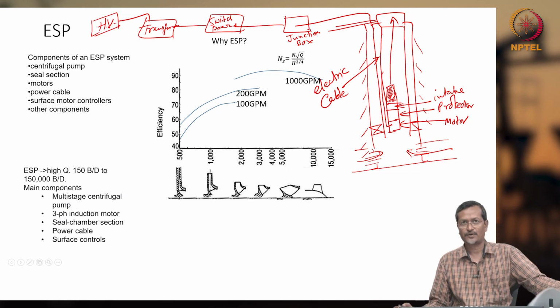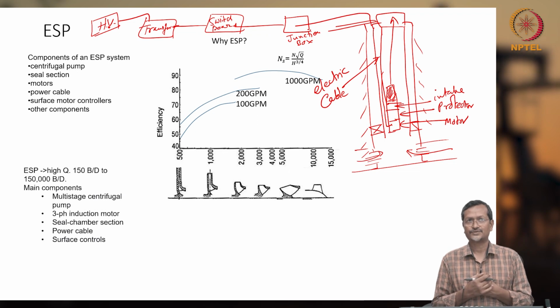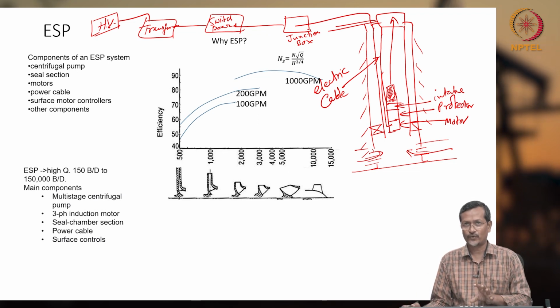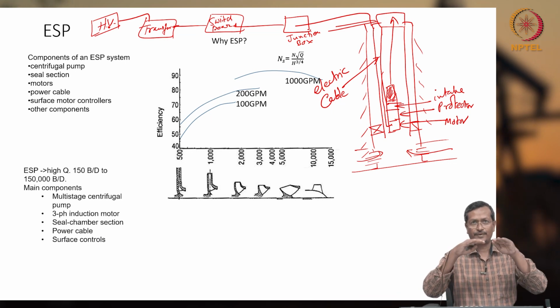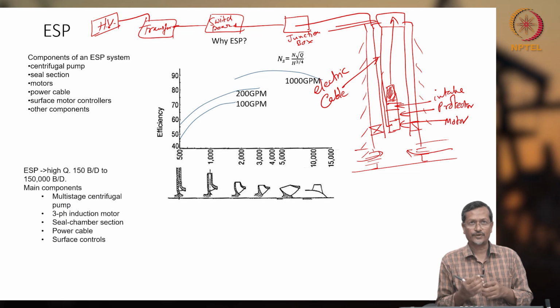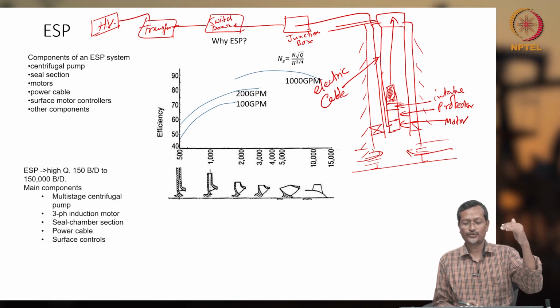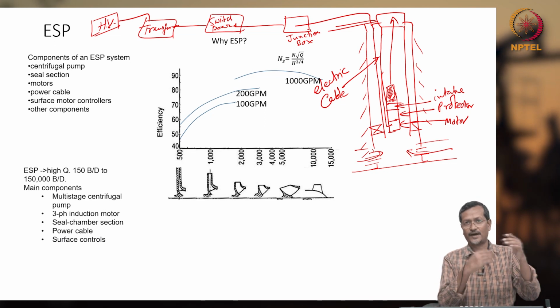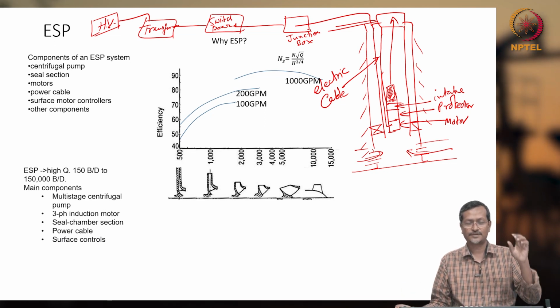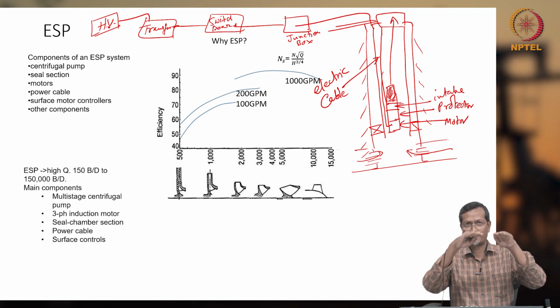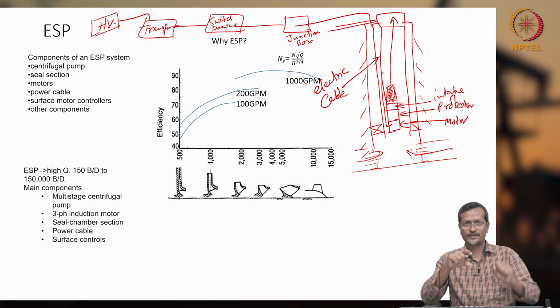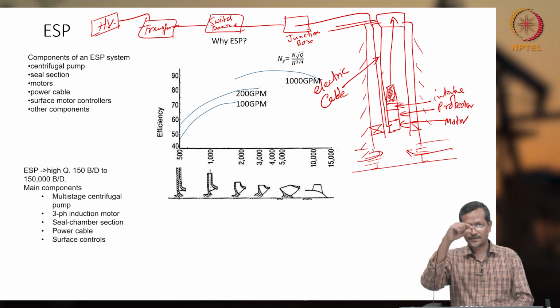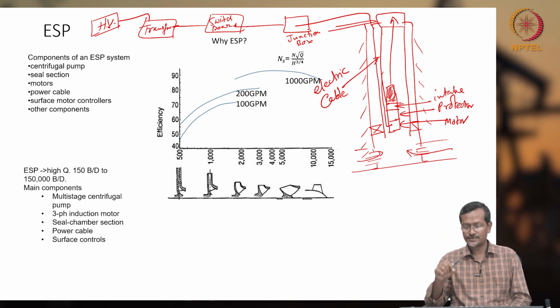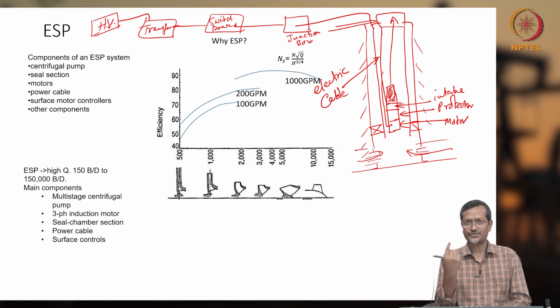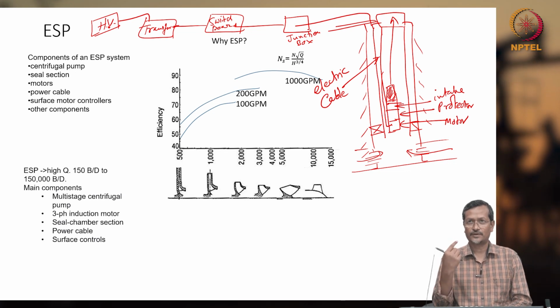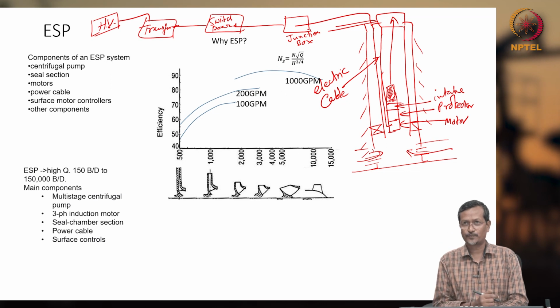The purpose of the transformer is this: if you have very high voltage, let us say 11,000 volts, and you want only 440 volts for your pumping operations, you have to reduce the voltage and supply it to the motor. If you give 10,000 volts to your motor, the motor will get burnt. At very high voltage, the system will fail. So in the step down transformer you reduce your voltage, then you pass it on to the switchboard and junction box, and that electric current moves towards your motor. Then the motor runs, and the motor shaft transfers power to the intake through the protector intake section.